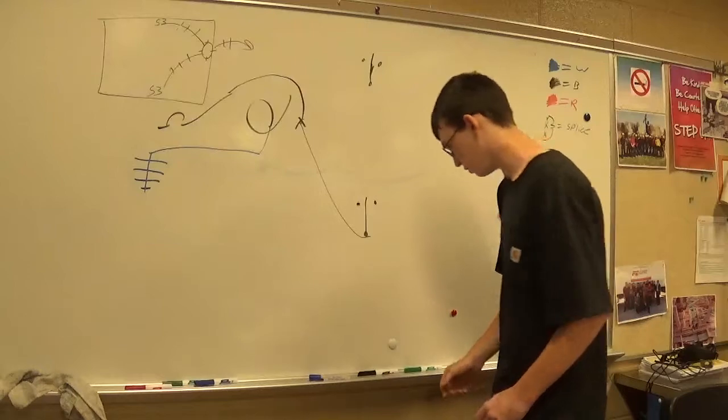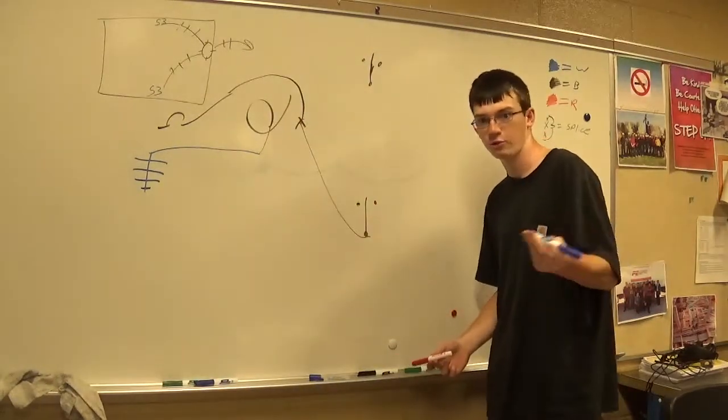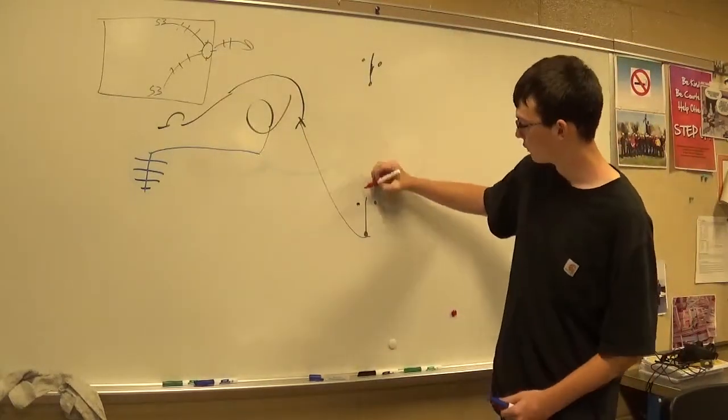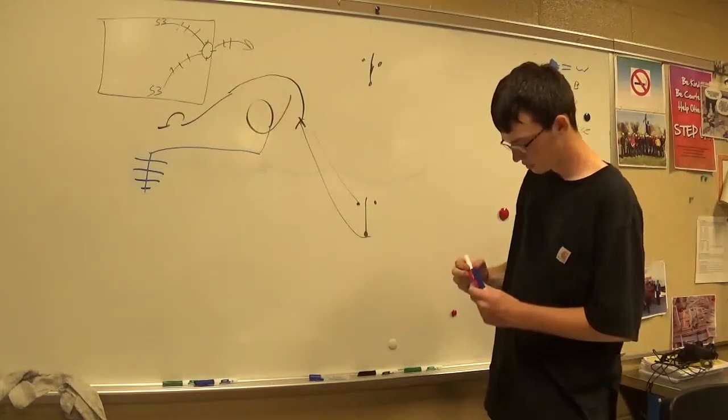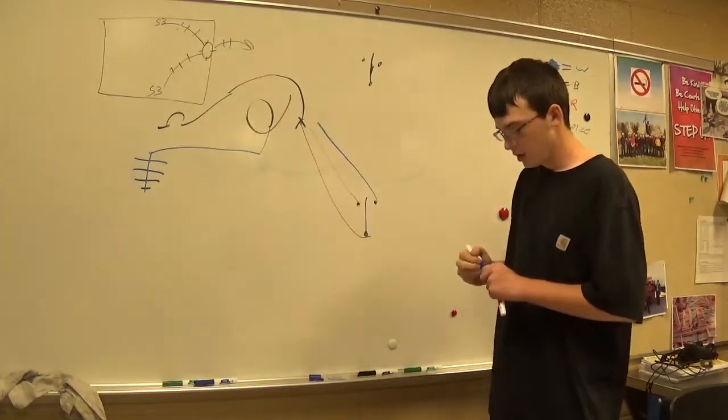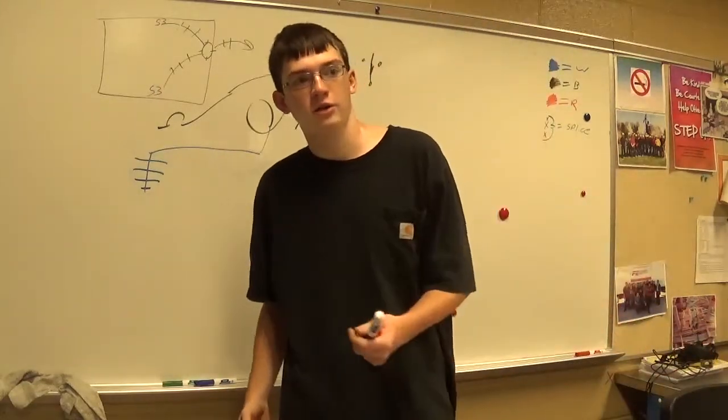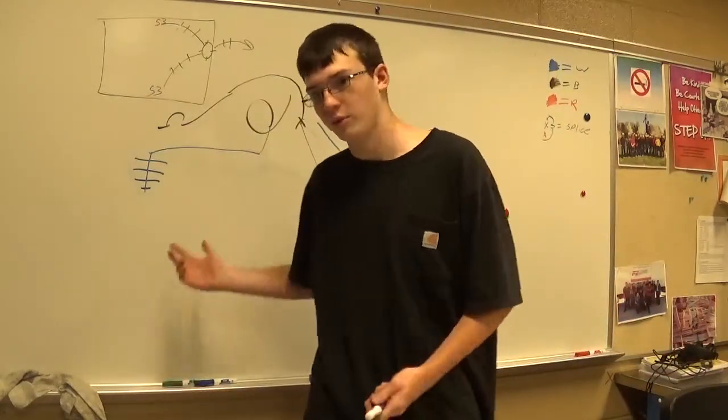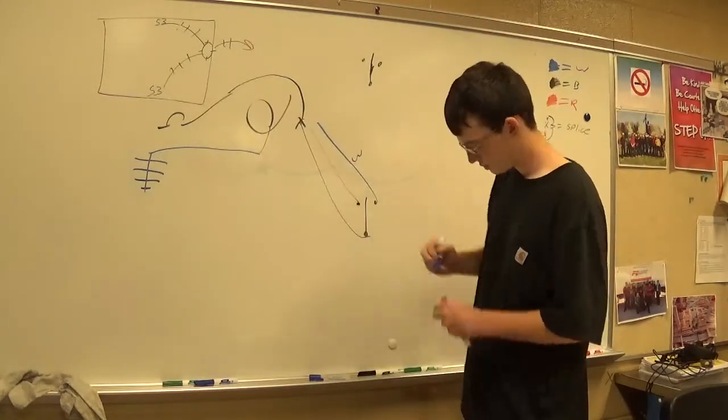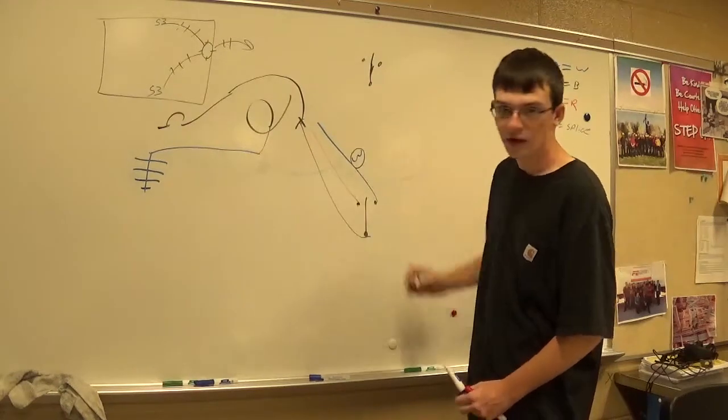Now your travelers are going to be white and red. Again, I know it's blue because you can't write white on a whiteboard. Your traveler comes off, back to the main box. Same thing with your white. Now with the code, the IRC code, NEC, same thing with that. You cannot use a white as a live wire, such as a black or a red. So what you do is take the white and you put a black circle around it to relabel it as a black white.